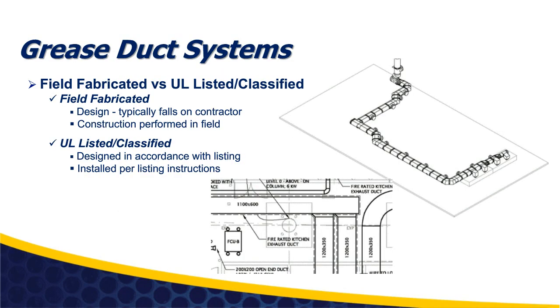So if I look at the design and who's going to be responsible for it, field fabricated products, really design ends up really kind of falling back on the contractor for the most part. I don't believe most engineering firms probably detail out a grease duct system, and the sheet metal contractor typically is going to be responsible to make sure that he's constructing that duct, he's got the supports in the right place, clean out access doors are acceptable to local jurisdiction. And then the insulation contractor is really going to be responsible to make sure that when he applies that insulation after it's gone through inspection, that he's doing it compliant with the insulation manufacturer's published information. So it's really dependent on proper construction that's going to be performed in the field.